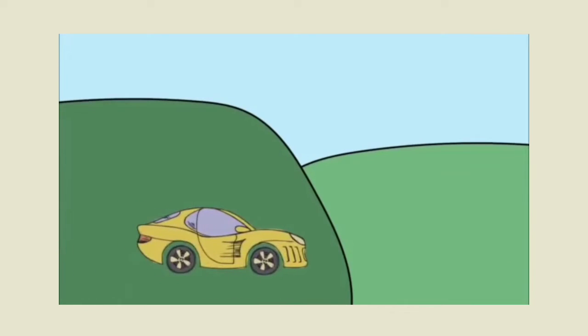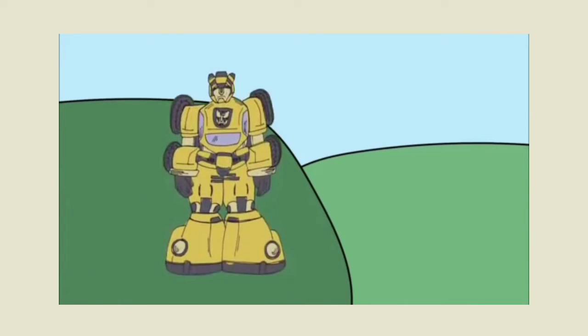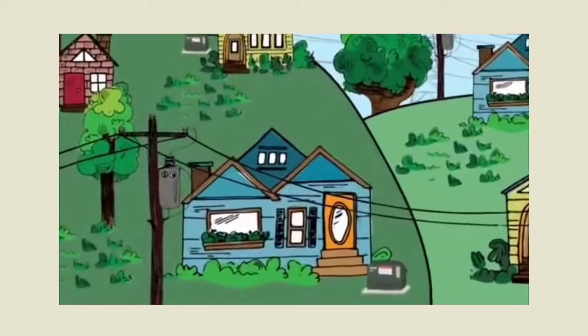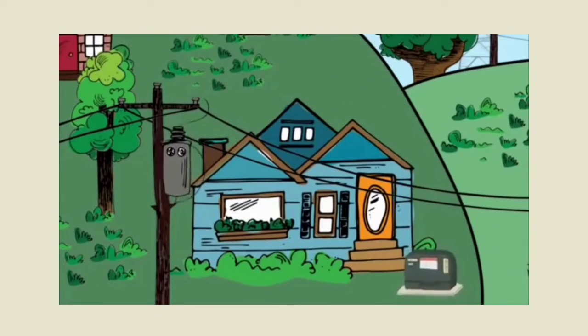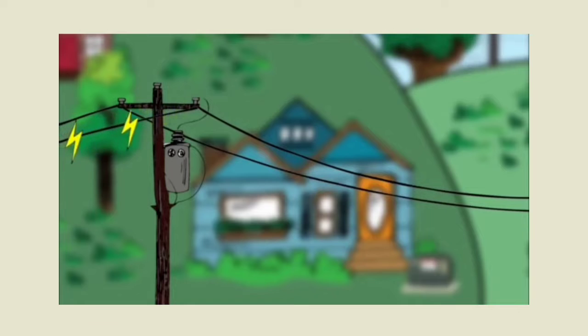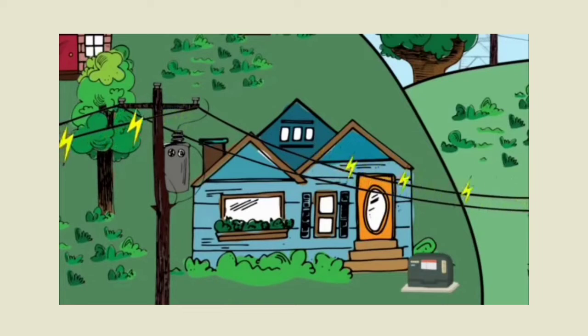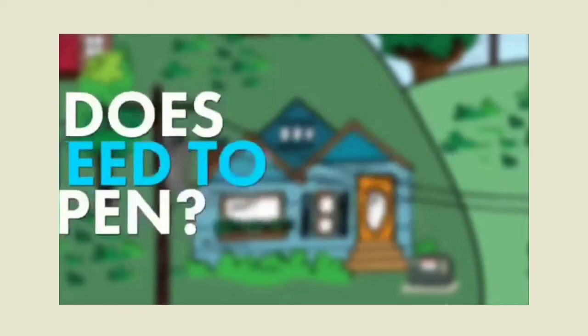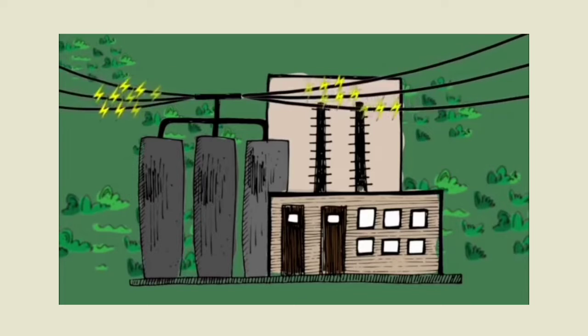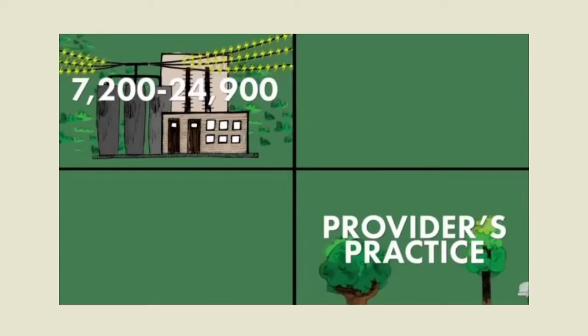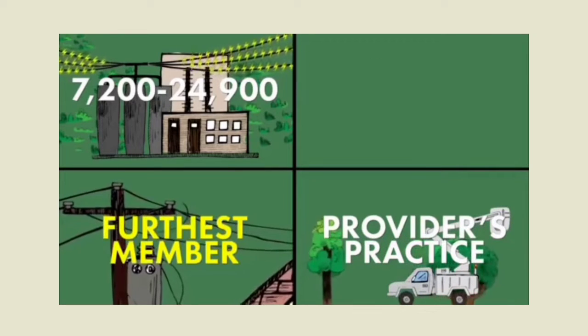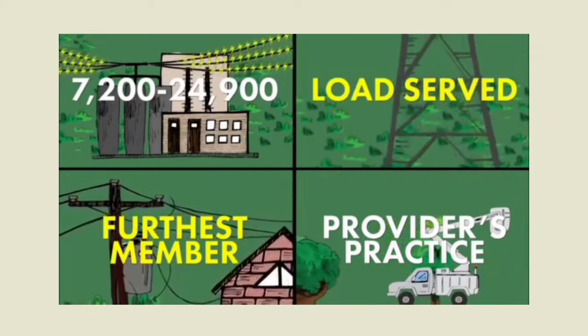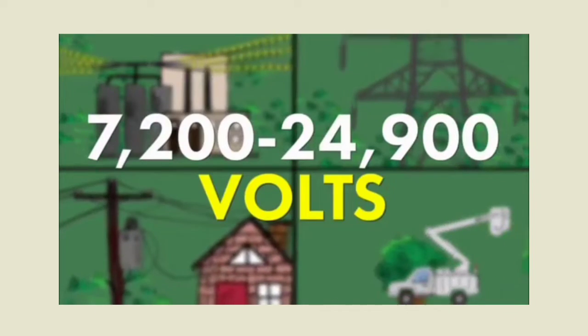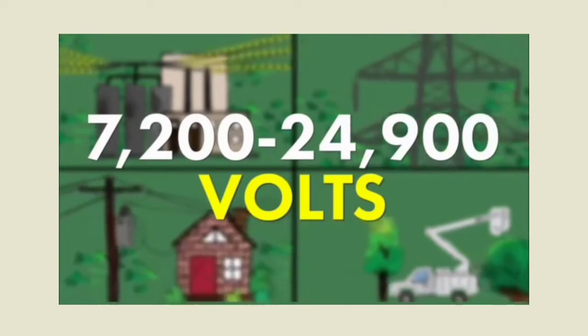Let's talk about transformers. Not the machines that transform from cars to combat robots you see in the movies, but the kind you see at the top of utility poles or on the ground in your neighborhood. Transformers are used to step electric voltage up or down before it makes its way to its final destination. Why does this need to happen? Original power distribution voltage can range from 7,200 to 24,900 volts, depending on your electric utility provider's practice, the distance to the furthest member, and the amount of load served. That's much too high a voltage for safe home or business use.